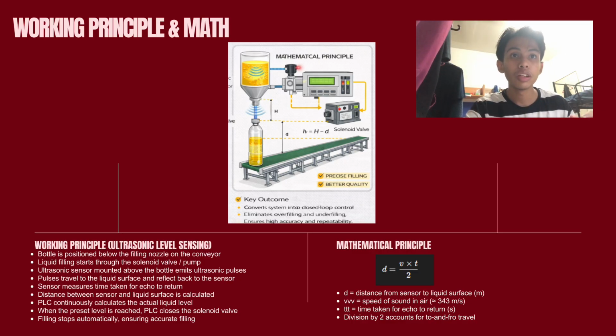Next, the ultrasonic level sensor measures the liquid level inside the bottle without direct contact. The sensor emits ultrasonic waves toward the liquid surface and measures the time taken for the echo to return. Using this time delay, the distance between the sensor and the liquid surface can be calculated. The distance is calculated using the formula where V is the speed of sound in air and T is the time taken for the signal to return. Once the required liquid level is reached, the PLC closes the solenoid valve to stop filling.